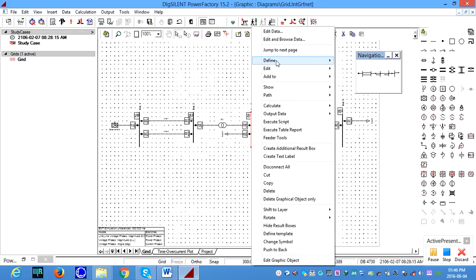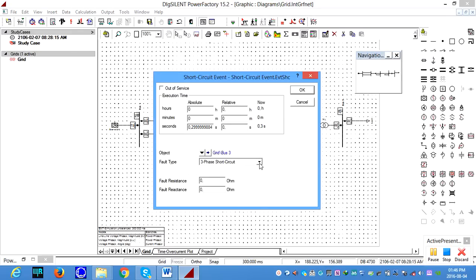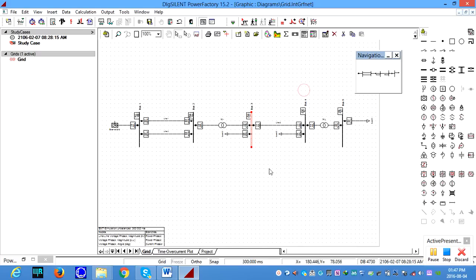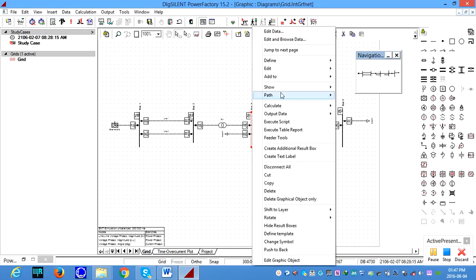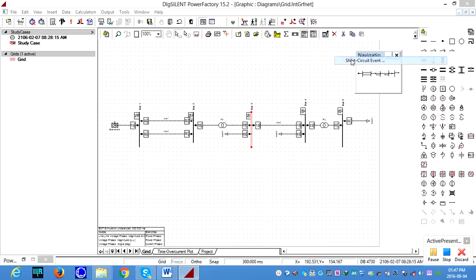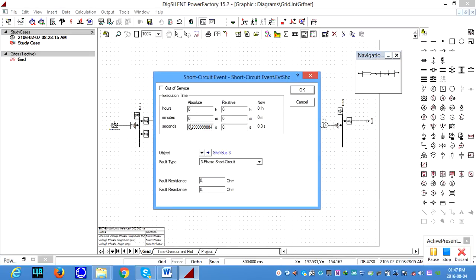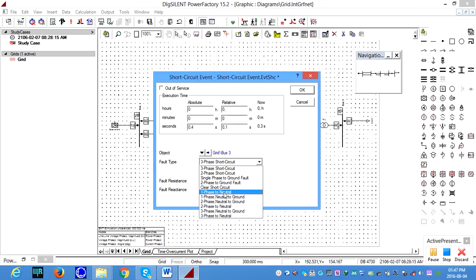Next you need to define the ground faults. So let's say you want to define a single phase to ground fault. It means we can create it at 0.3 seconds. We leave 0.2 to 0.3 seconds for the system to build up the voltage, but at 0.3 seconds we can initiate a ground fault on phase A. We can do it for phase ABC, but in this case let's leave it as phase A. And we need to clear the ground fault. Again go there, we need to define a short circuit event, and at 0.4 seconds we clear the short circuit which we defined already.